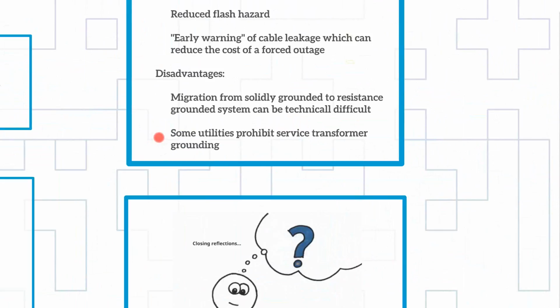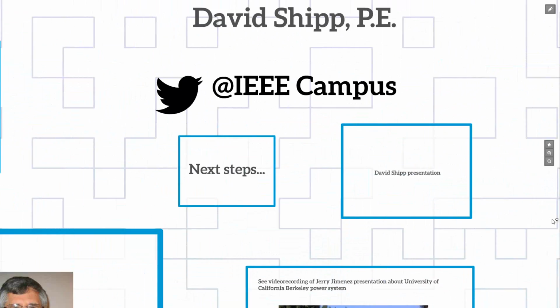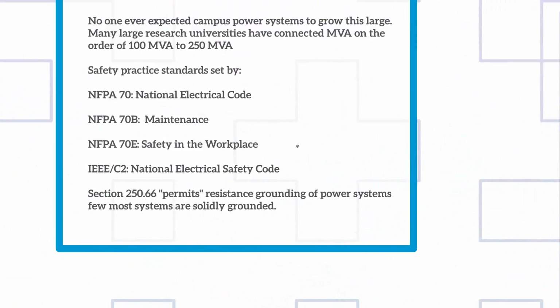So there's a lot of things we've learned in the last 10 years doing arc flash incident energy studies, and the safety driver is what gets more people's attention than anything. So I'm very pleased with what Tammy's been doing in that arena to give us some real-world empirical data and models that we can actually do something with without being PhDs for every individual system. So I guess what I'm saying is at the medium voltage level, there is a 50-year track record of low-resistance grounding in North America within the process industries. All we've got to do is take what we learned there and modify it 10 or 15% and put the concept into your university campus type setting. And then you get the same benefits that the chemical plant gets.